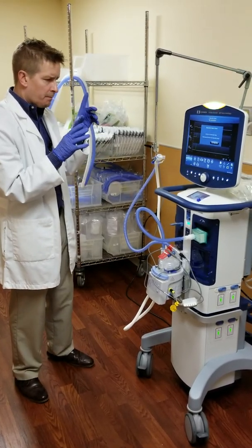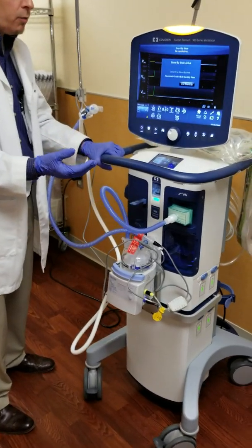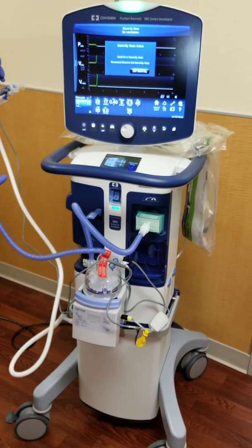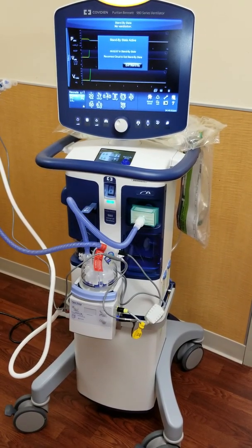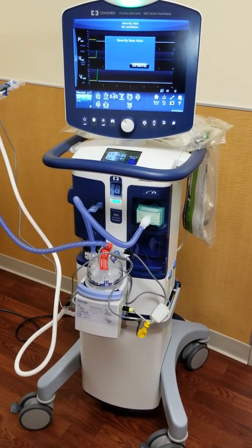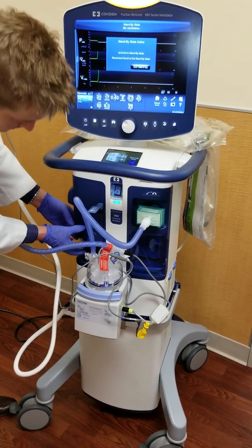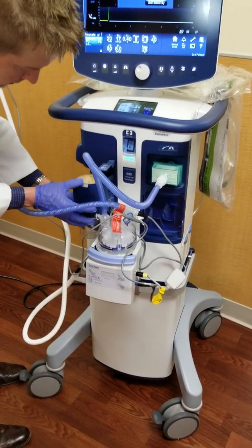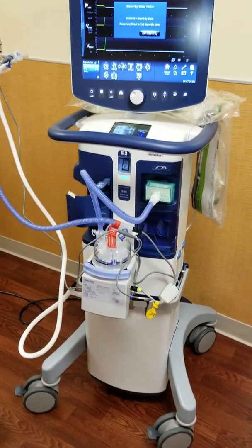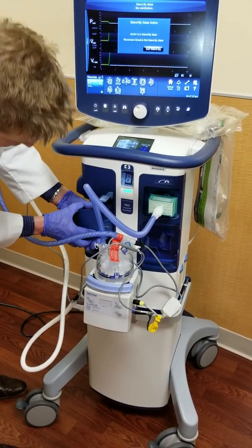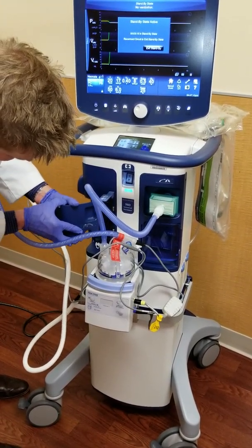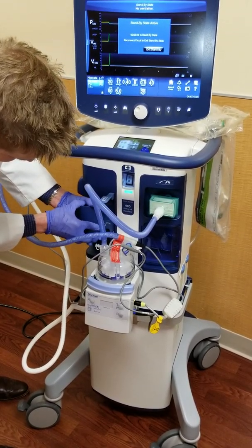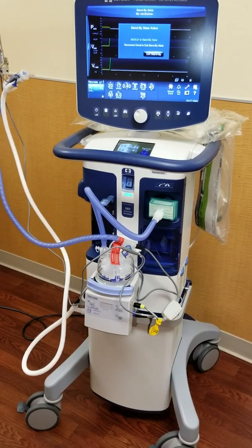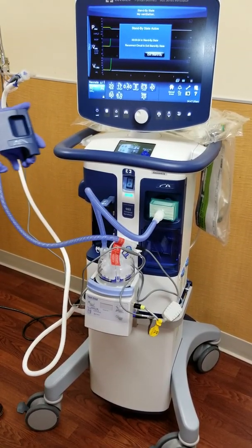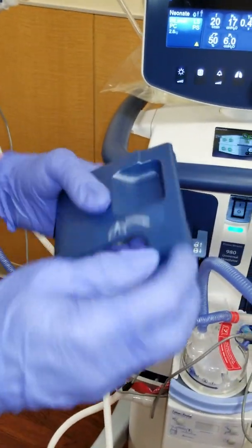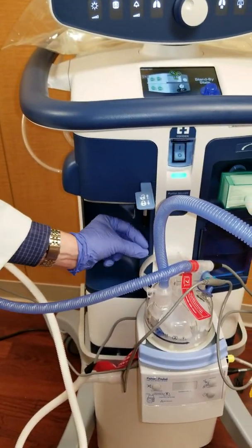So, in the event here at Advocate Broman, for our neonates, we predominantly use the Aveas, but if in the event you need to use the 980s, this is what you're going to have to do. And this is not convenient. However, what you're going to need to do is remove the adult filter, remove the adult door, which just slides upwards. Go back, it goes in. There's the adult door. There is a special neonatal door. See this hole here, and this hole here. It goes on these pins here.